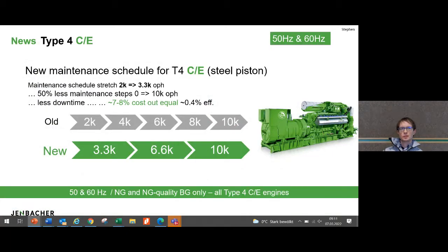So in addition to the improved efficiency, the structural strength and valve performance has really allowed that we can stretch the service interval. So for the valve clearances moving from 2K to 3,300, it actually reduces by 50% the amount of maintenance required around the cylinder heads every 10,000 operating hours. And this can be equivalent to around 0.4 efficiency gain in terms of service cost reduction.